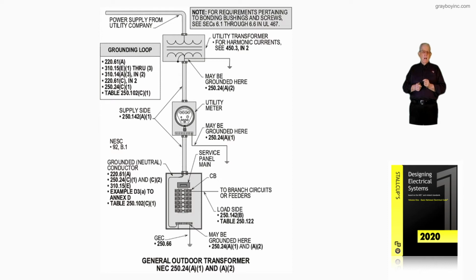And then if we looked at 250.24(C)(1), then again, we're dealing with grounding and bonding and the grounded conductor and the neutral conductor and the effective ground fault path. And then, of course, the summary table 250.102(C)(1), and again, we'll use 4/0 conductors and be consistent with that size. If we had 4/0 from the transformer in the illustration through the meter, terminating to a main, 225 amp, then that grounded neutral conductor you see there would have to be number 2, based upon the 4/0 conductors, and the number 2 selected from table 250.102(C)(1). But then you'd have to size it by 220.61 for neutral load.